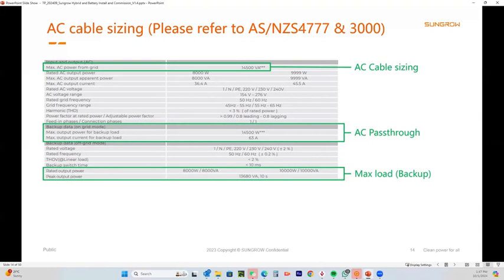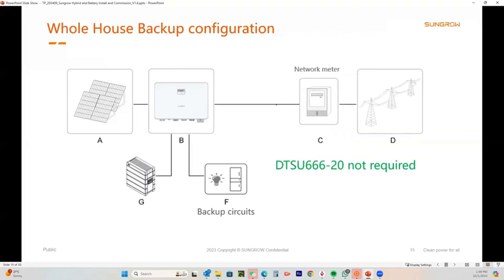Now bear in mind, when it is backup, the 8 kilowatt inverter's backup in off-grid mode is 8 kilowatts, and for the SH10RS, the backup maximum is 10 kilowatts. Another point to these inverters is with the 8 and the 10 kilowatt and the new 3-phase series, you can actually put the PV panel ratio at 200%. For an example, on the 10 kilowatt, the system could be passing 10 kilowatts AC out to AC and 10 kilowatts DC to the battery at the same time. So with the 8 and the 10 and the 15, 20 and 25 kilowatt models, you can have an AC-DC ratio of 200%.